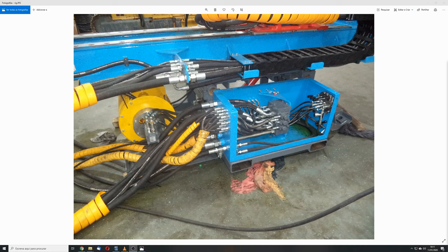Hi! In this video, I'm going to demonstrate a less common situation that you may run into when adjusting load sensing controls of certain open-loop variable displacement pumps, and I want to showcase a wireless system that I used to monitor the pressures and the flow during the adjustment process.